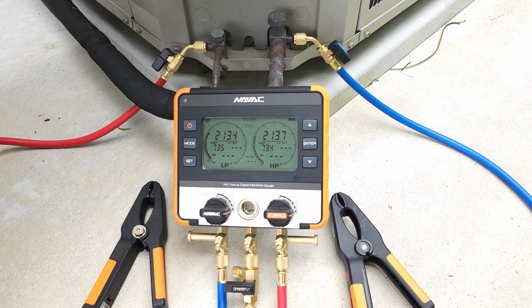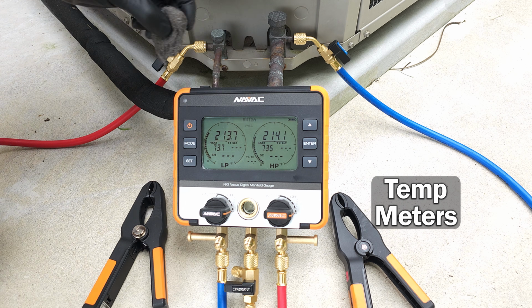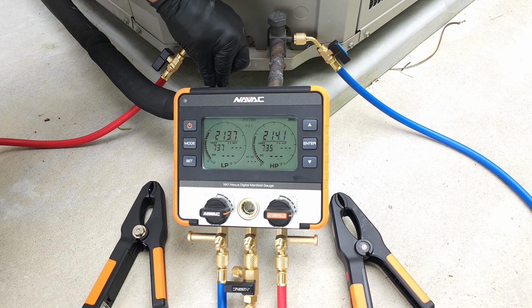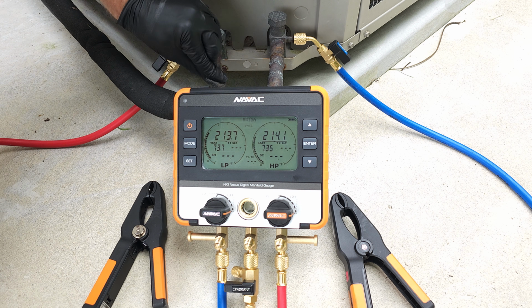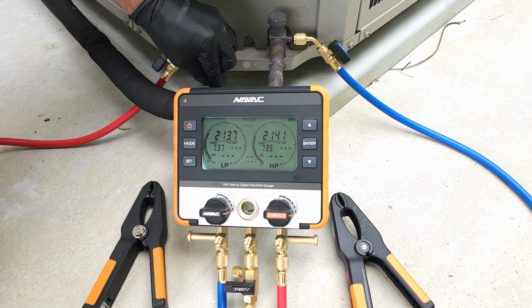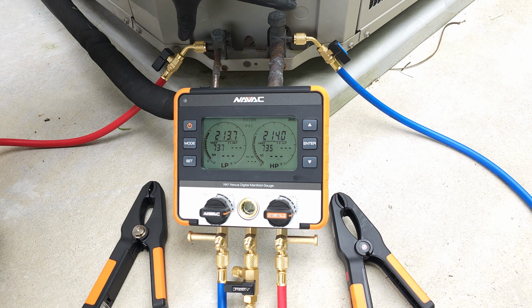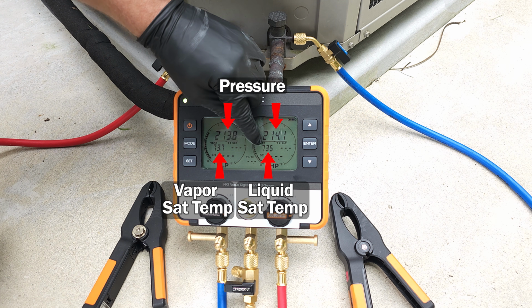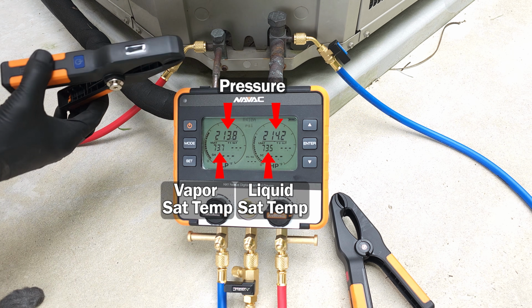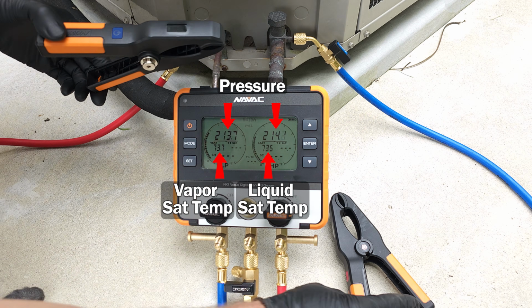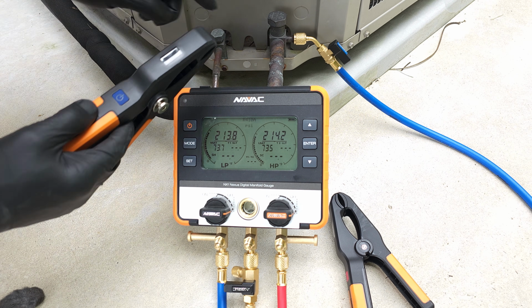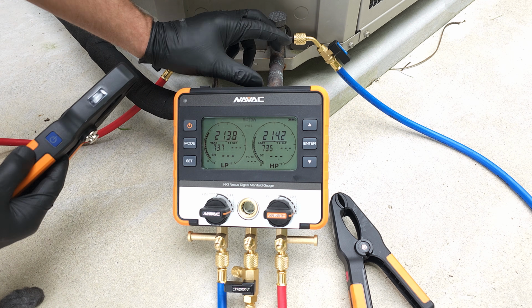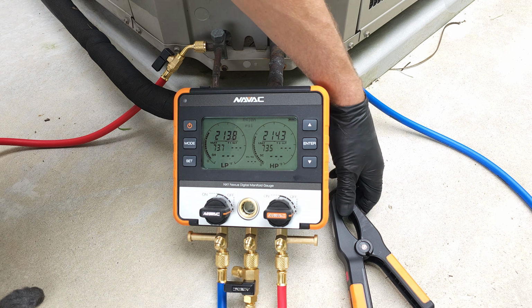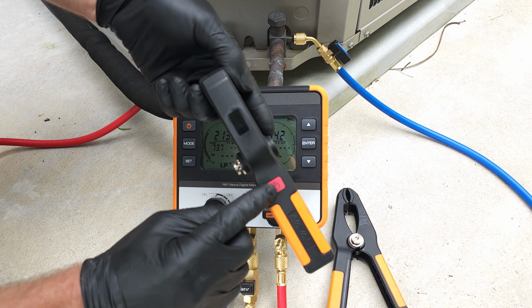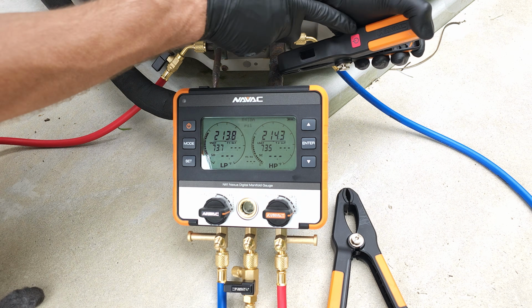And so now we're going to go ahead and connect our temperature meters. We can take some steel wool in order to just clean off the part of the tubing where we're going to be measuring the temperature. Remember, we need pressure to convert it to saturated temperature, which right there is the liquid sat temp, vapor sat temp. And then we need our line temperature as well. So this is our blue one. This is going to connect onto our large low pressure side. And this one right here is our red.